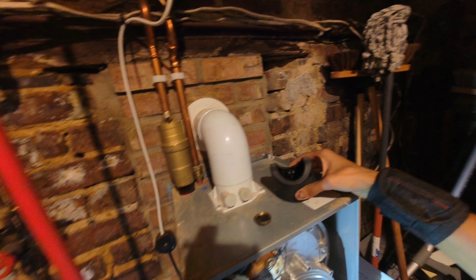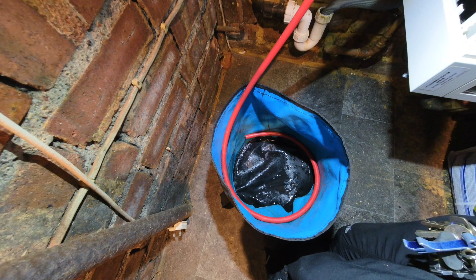Okay, burner and everything is all back together. Now I'm going to clean out the filter. I've taken off the magnet which holds all the dirt in there. This is an open vented system so I expect a fair bit of dirt - let's see, get this open. It's not actually that bad. Let me flush through for a little bit. Yeah, that's pretty clean.